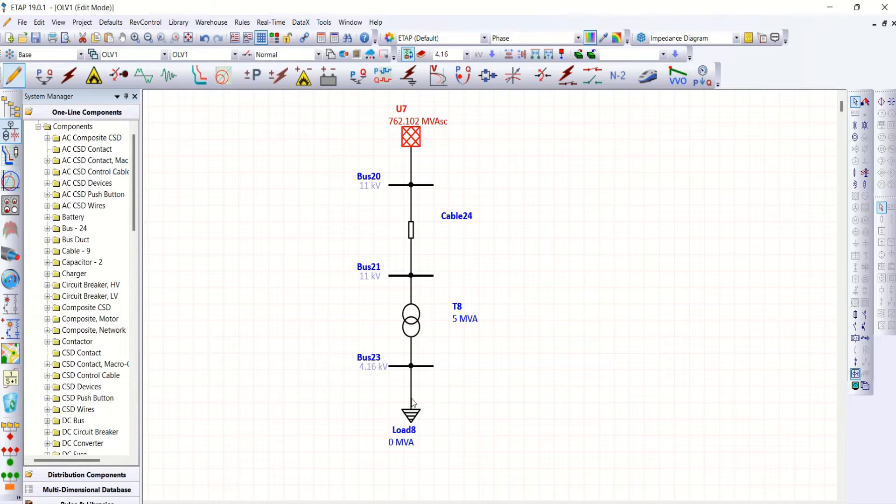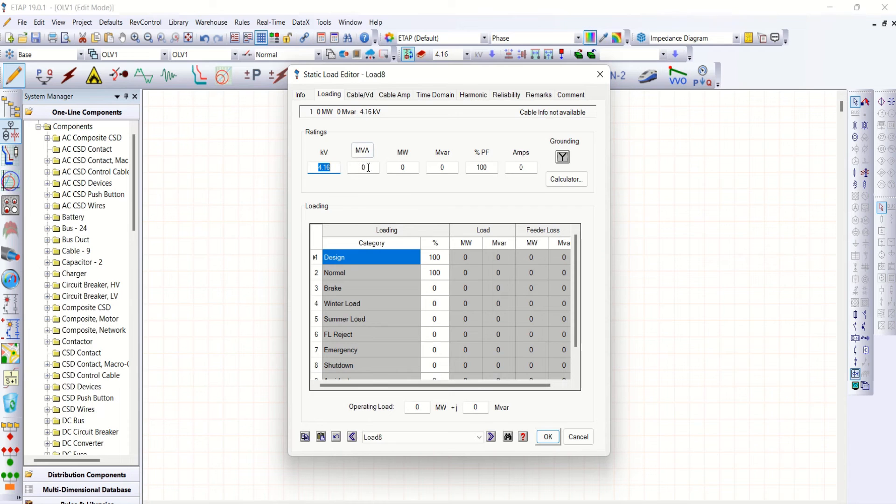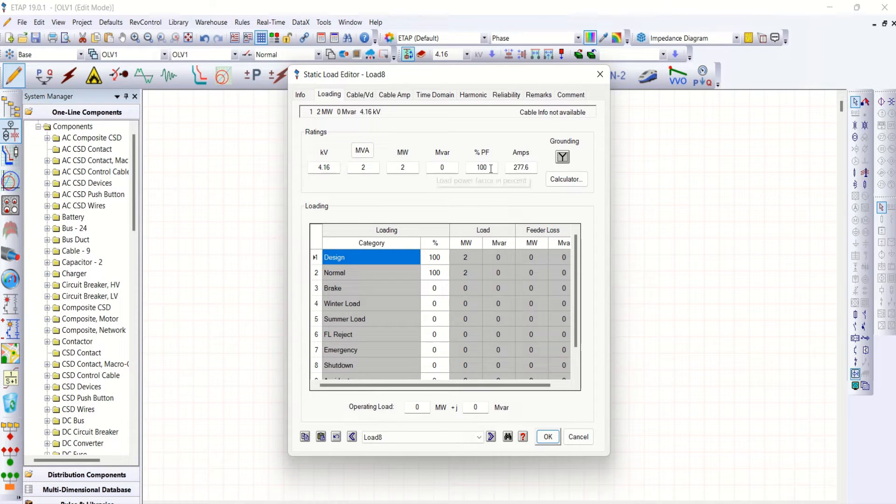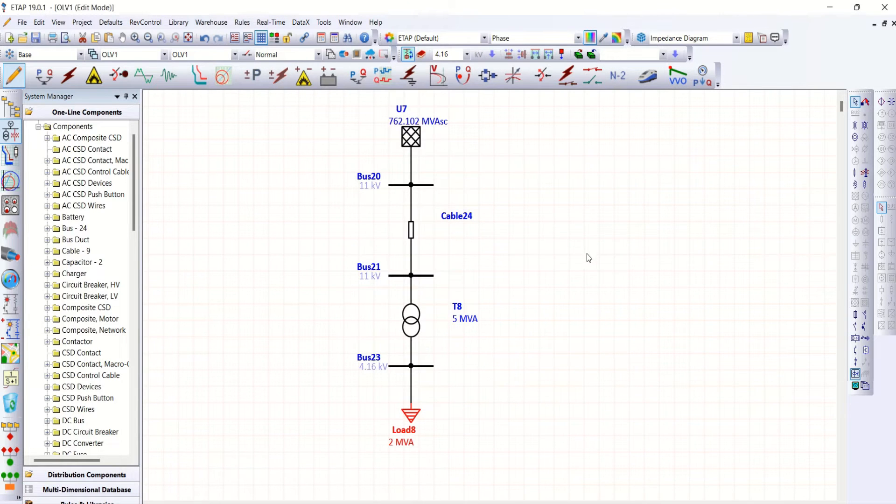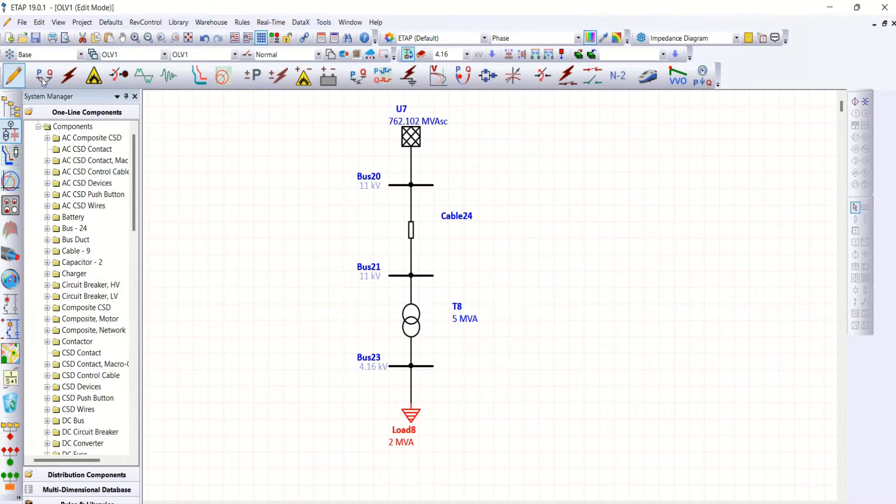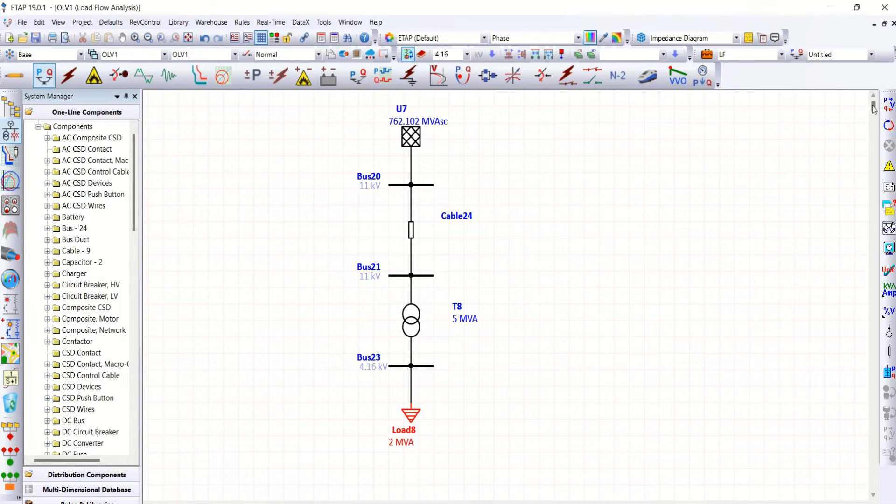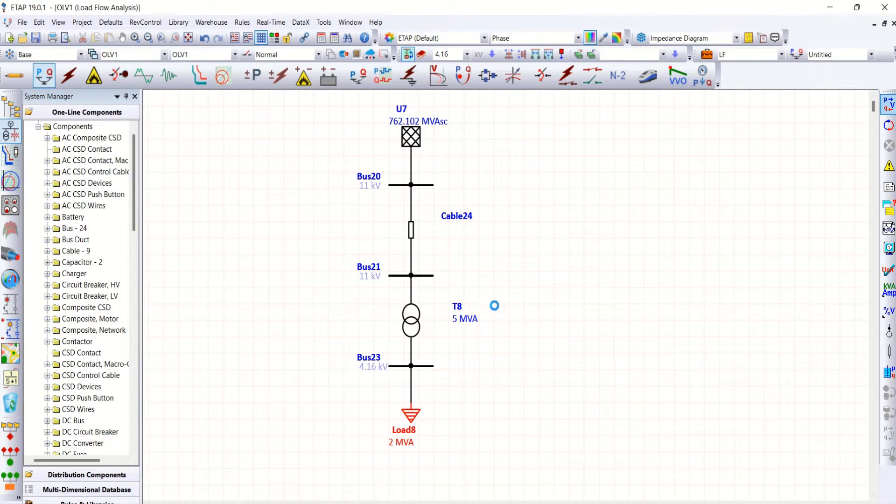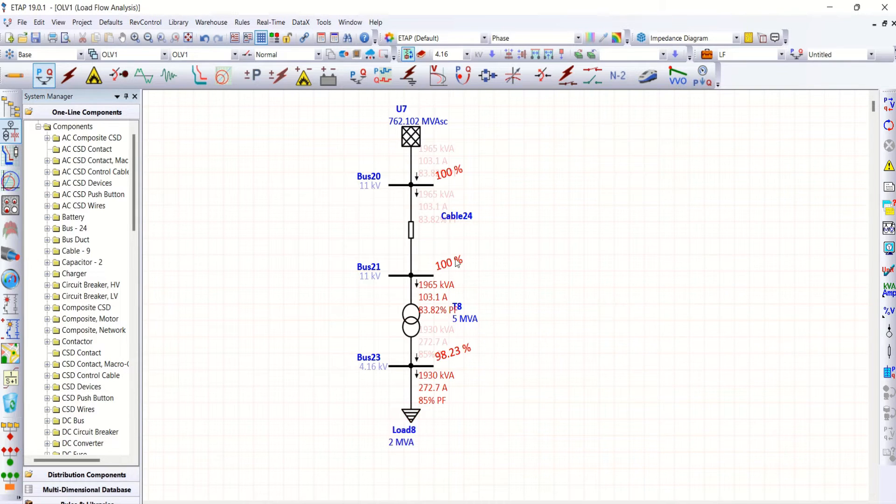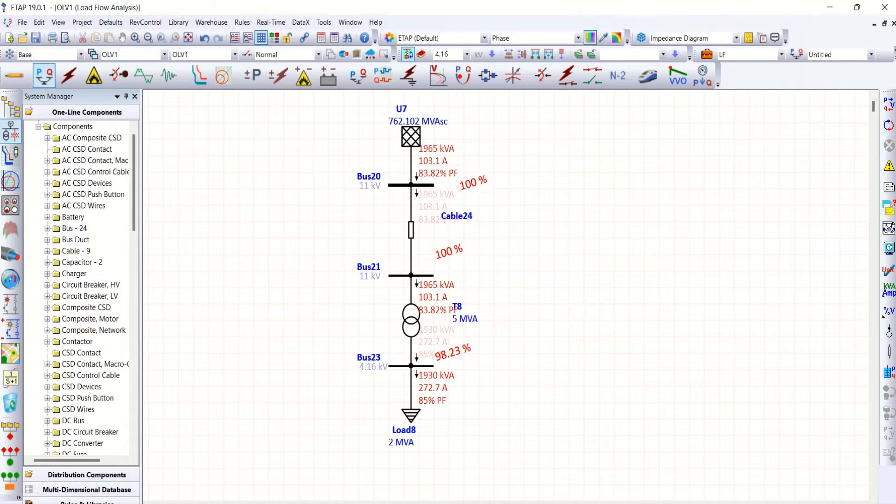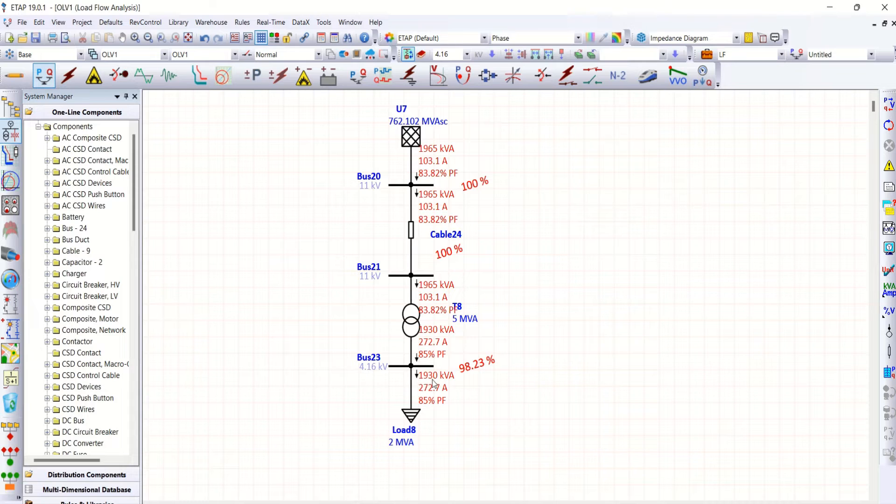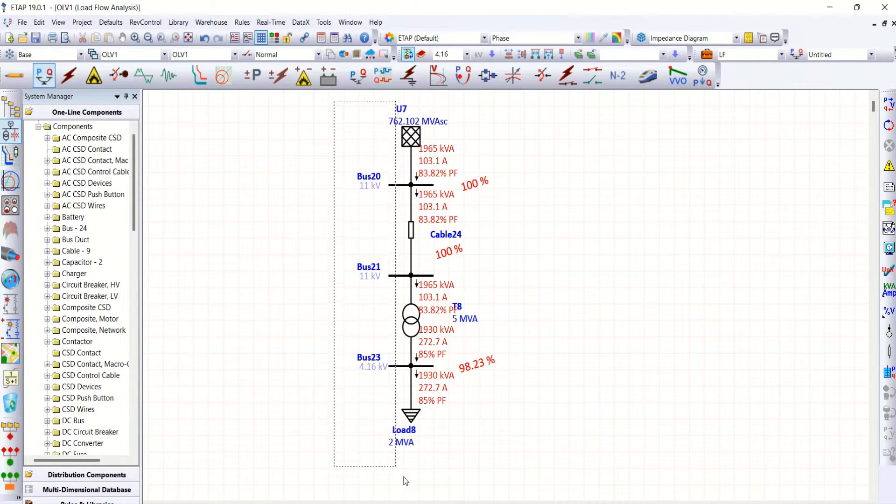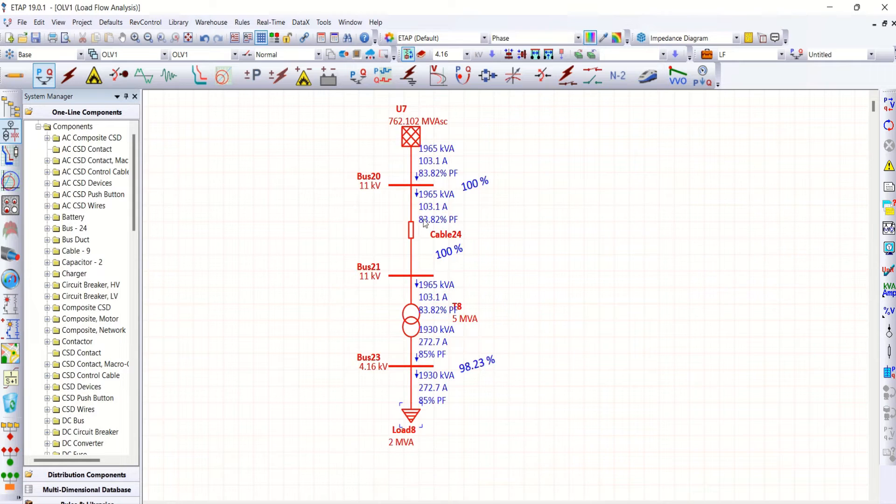Okay, then load side. Let me take 2 MVA load, 85% power factor. Let me run load flow in order to check whether the model is right or wrong. Yeah, it's working. So because of static load it is taking 1930 kVA value rather than 2 MVA.